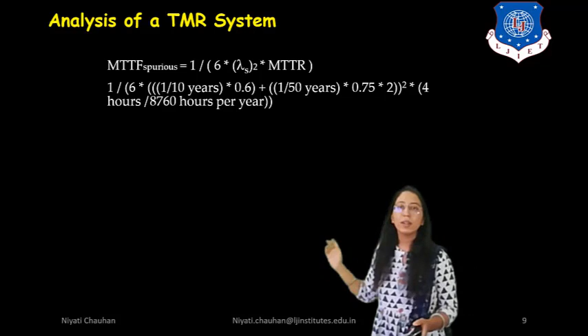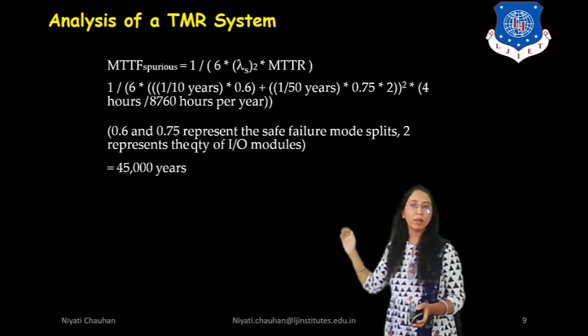MTTFS is equal to 1 upon 6 into lambda into TR. So 1 upon 6 into 1 by 10 years into 0.6 plus 1 upon 50 years into 0.75 into 2, and into 4 hours divided by 8760 hours per year. So finally we can say that 0.6 and 0.75 represent the safe failure mode split and 2 represents the quantity of the input-output module. So that is equal to 45,000 years.